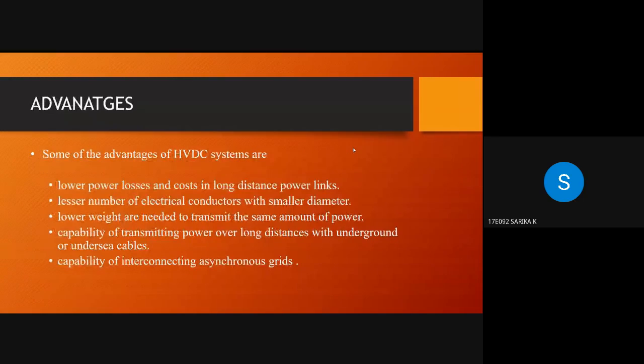Advantages of HVDC: lower power losses and cost in long distance power links than AC transmission. It requires a lesser number of electrical conductors, thus also reducing the cost. Lower weight is needed to transmit the same amount of power which is transmitted via AC transmission. Capability of transmitting power over long distances with underground or undersea cables. And it is also capable of interconnecting asynchronous grids.